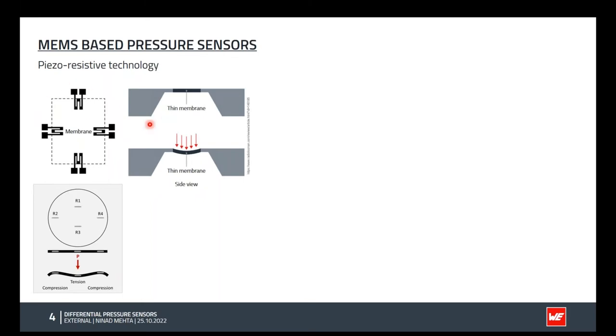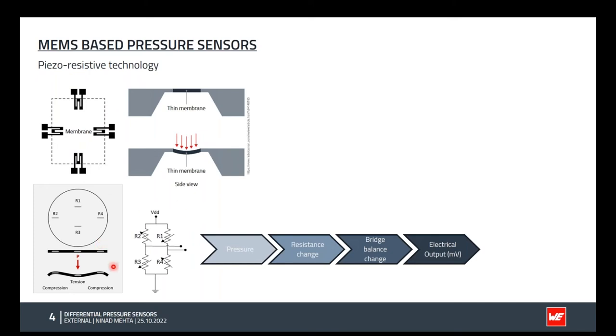So these piezo resistors are electronically connected in a Wheatstone bridge, and they are supplied with voltage. Whenever there is a pressure from the top side, because of this pressure or force, the resistance of the piezo resistor will change, and then the bridge will be in imbalance, and we will have some voltage drop across the Wheatstone bridge. This voltage drop in the end is directly proportional to the pressure being applied on top of the membrane. So we will have some millivolt output. It is important to notice here that this output is purely analog, and it is also not calibrated or compensated.